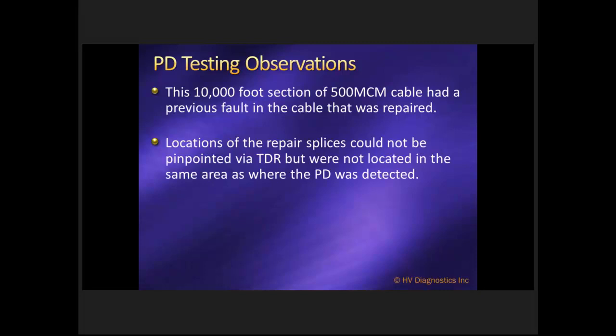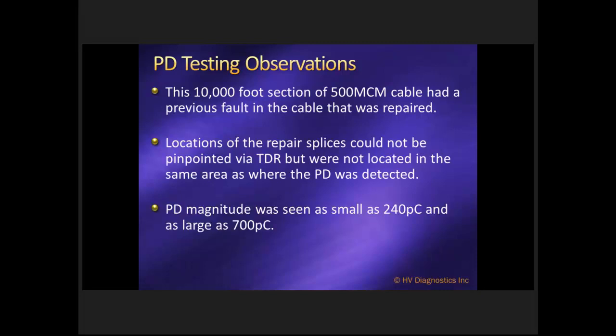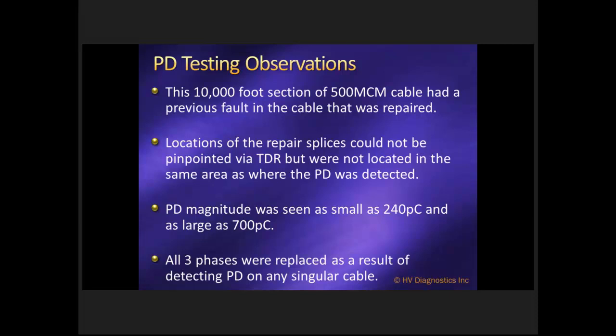The location of the replaced devices could not be pinpointed. This cable had obviously been repaired before, so we tried to locate the splices. They were not GPS tagged, as they were done after original construction. We couldn't locate them with the TDR. But from all accounts, it was nowhere near where the PD was detected. So clearly, the PD was inside the cable section. The amplitude of PD was seen as small as 240 picocoulombs and as large as 700 picocoulombs. As a result of this, all three phases were replaced. They were not interested in trying to help the cable over the potential issue that they'd come up with before the testing.